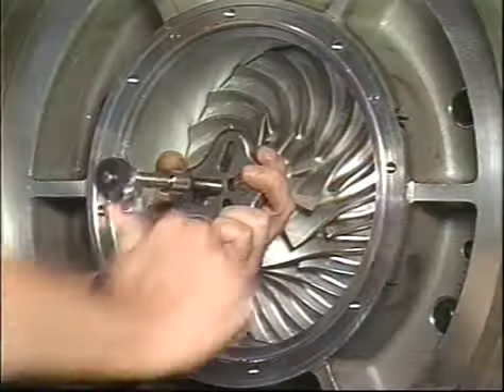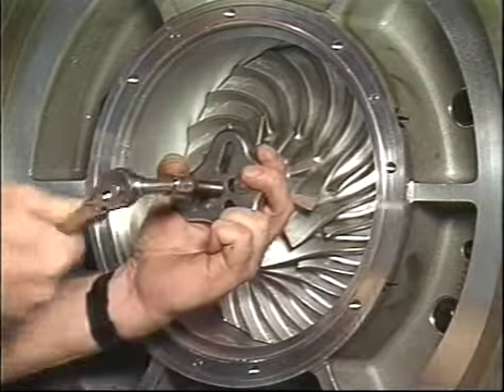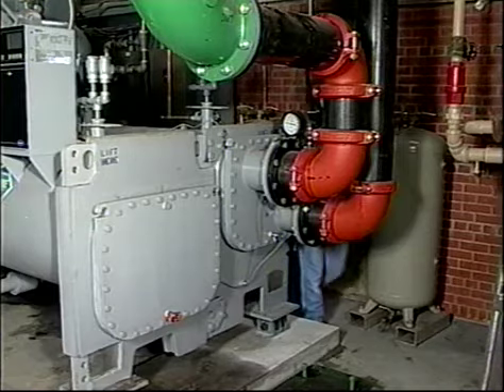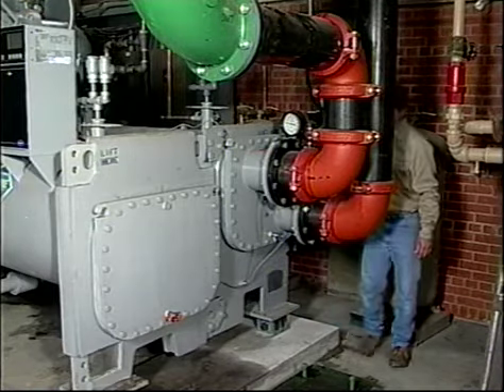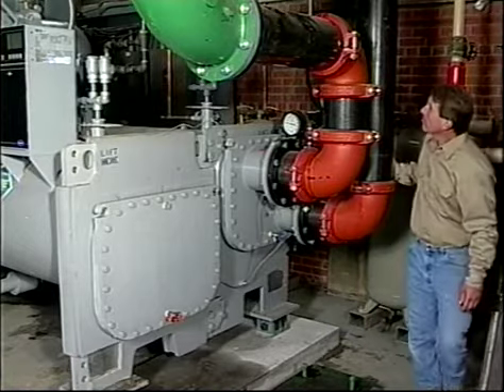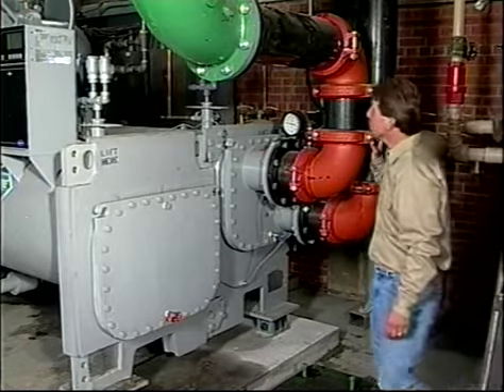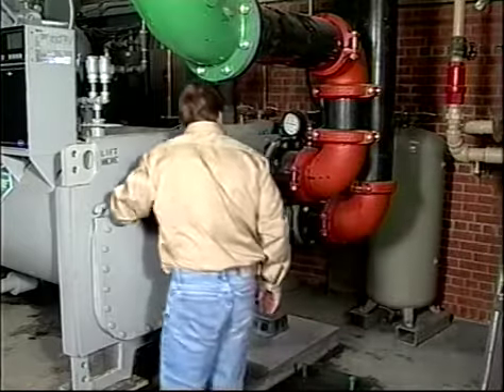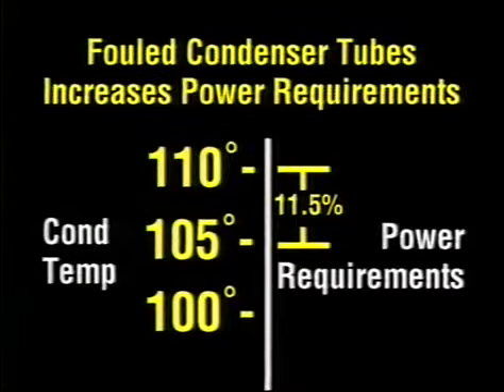The need for good maintenance goes beyond just avoidance of problems. If heat exchanger tubes become fouled or water flow rates or temperatures are not proper, operating efficiency can become seriously affected. For instance, if condenser tube fouling causes a 5 degree increase in condensing temperature, chiller capacity will be reduced and the power requirements will increase by 11.5%. Tube cleanliness, then, is of great importance.